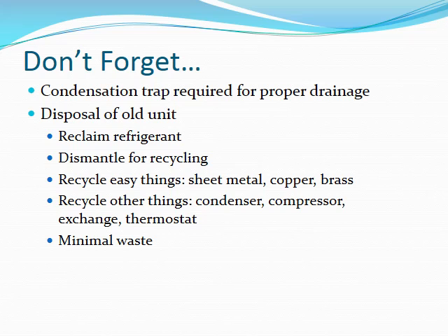In disposing of it, the first thing was to reclaim the refrigerant. Then we dismantled the whole system for recycling. The easy things to recycle included the sheet metal, the copper, and the brass. Some other things are a little bit more difficult to recycle, but we had no problem doing it. It was the condenser, the compressor, the exchange core, and then the thermostat. My main thing here was to minimize the waste.